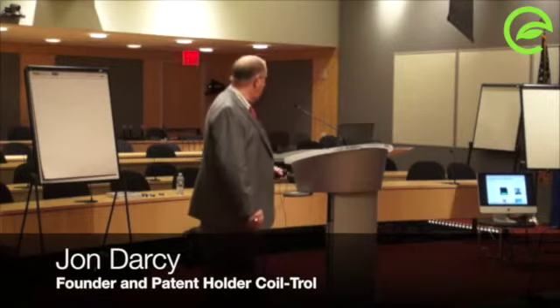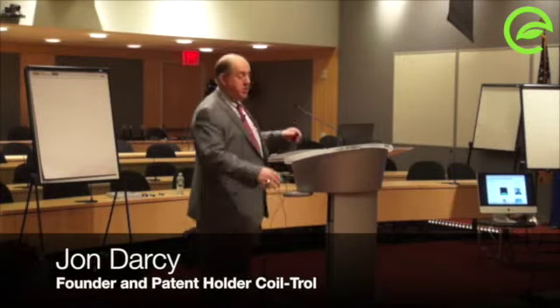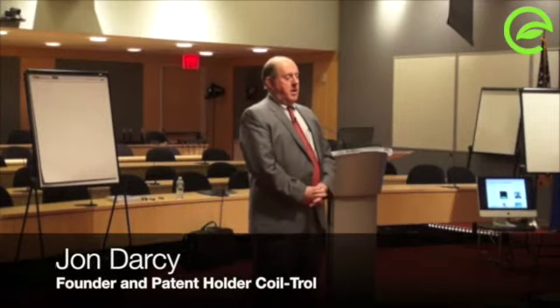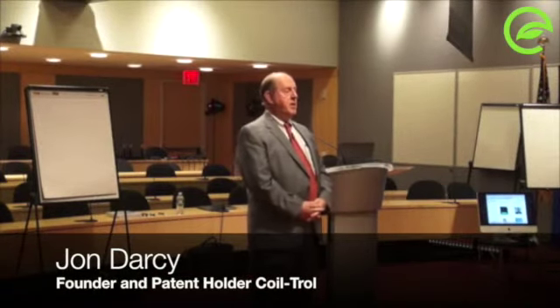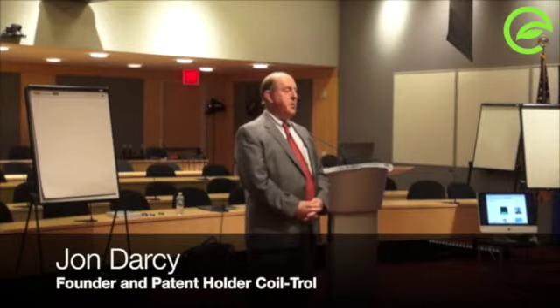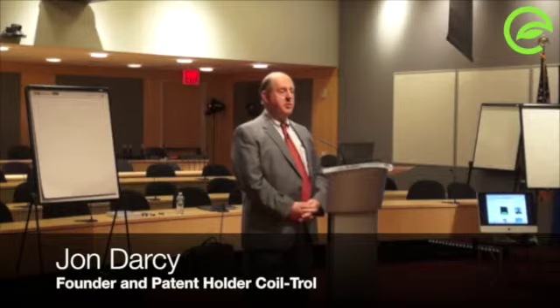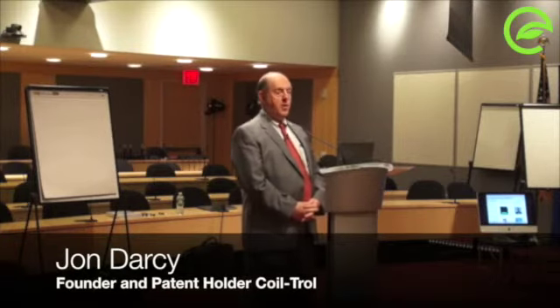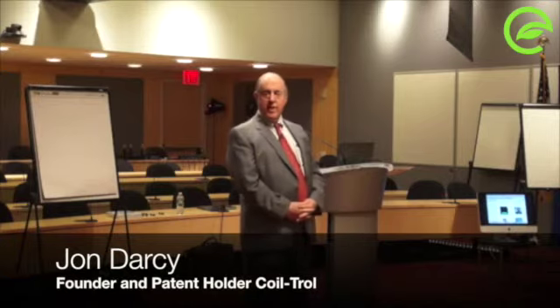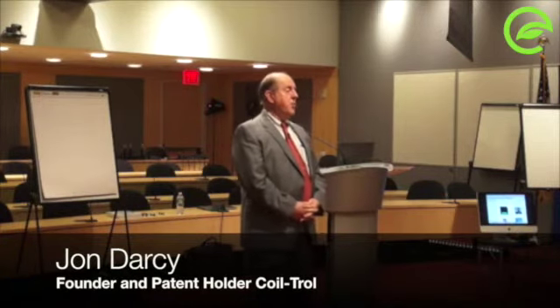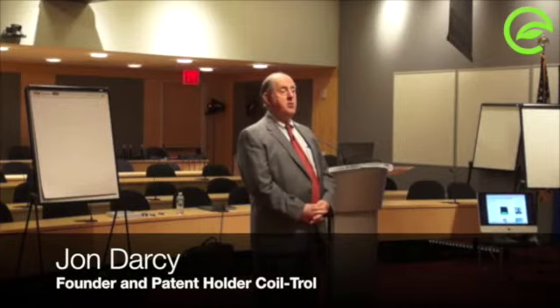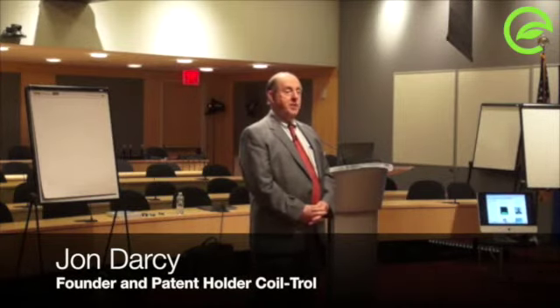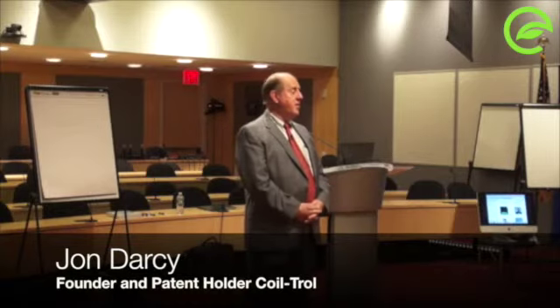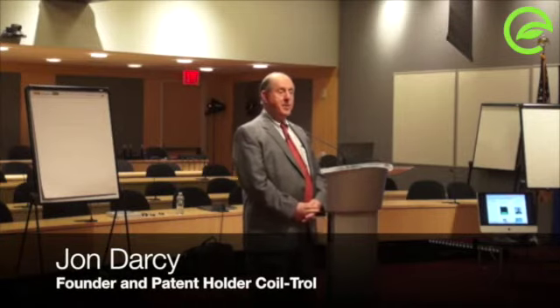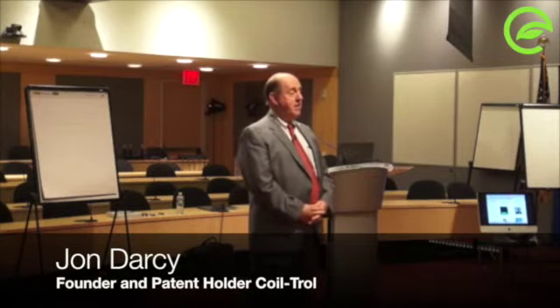By the way, when we talk about running chilled water temperatures and when you start your building up, I see a lot of people in the morning try to bring the building down and try to flywheel the building through the day. They really don't know if it's working or not, but they're not getting any complaints, so it works. But the reality is there aren't enough BTUs to flywheel in the building. The air is changing 4 or 5 times an hour. You can't flywheel that building, but you can pull the humidity down.